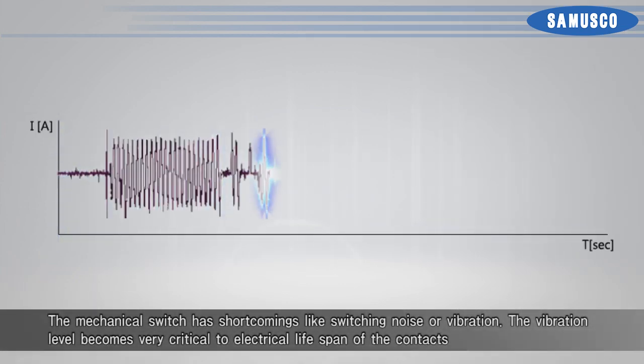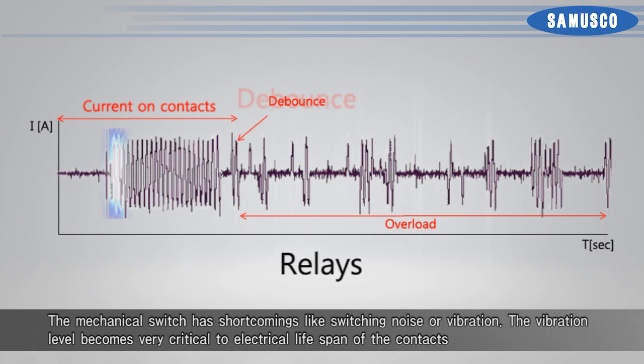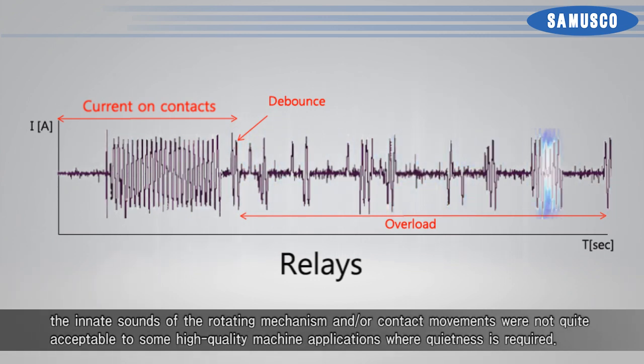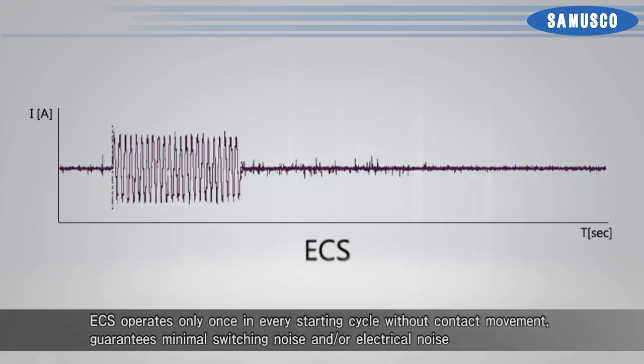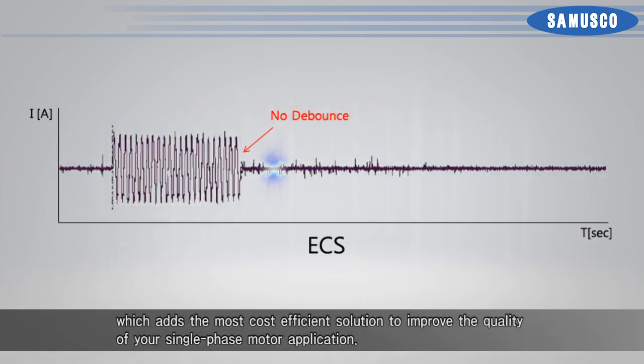The mechanical switch has shortcomings like switching noise or vibration. The vibration level becomes very critical to the electrical lifespan of the contacts because the number of switching sequences for each starting cycle can increase rapidly as the starting time increases. In addition, the innate sounds of the rotating mechanism and/or contact movements were not quite acceptable to some high-quality machine applications where quietness is required. ECS operates only once in every starting cycle without contact movement, guaranteeing minimal switching noise and/or electrical noise, which adds the most cost-efficient solution to improve the quality of your single-phase motor application.